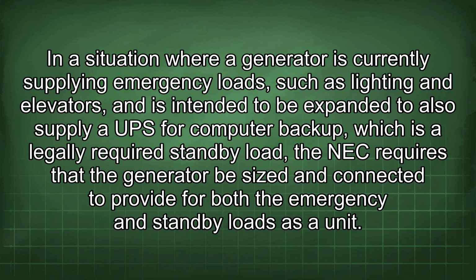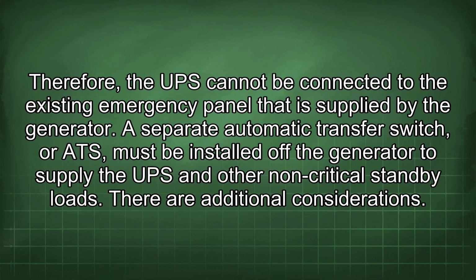In a situation where a generator is currently supplying emergency loads, such as lighting and elevators, and is intended to be expanded to also supply a UPS for computer backup, which is a legally required standby load, the NEC requires that the generator be sized and connected to provide for both the emergency and standby loads as a unit. Therefore, the UPS cannot be connected to the existing emergency panel that is supplied by the generator.